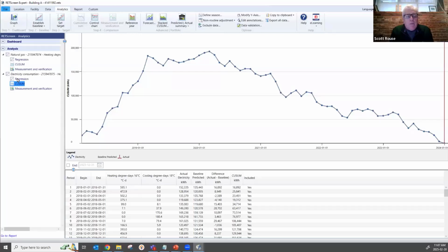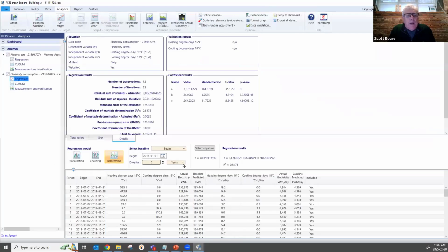Yeah, it's very powerful. We use these CUSUM on all of our EMAPs, and we update it on a regular basis. So as Stephen pointed out, if you see it going up, there's an increase. If you see it going down, there's a decrease. If you see any change in slope, something has happened. And that sparks the conversation between the property manager, operations, your vendor.